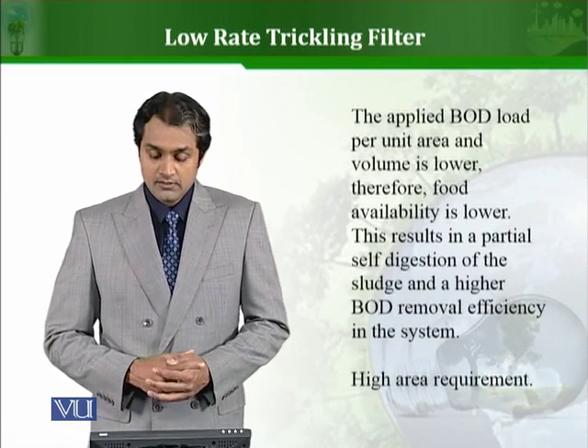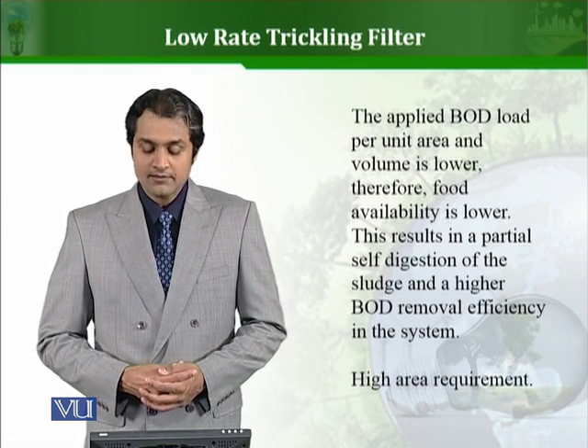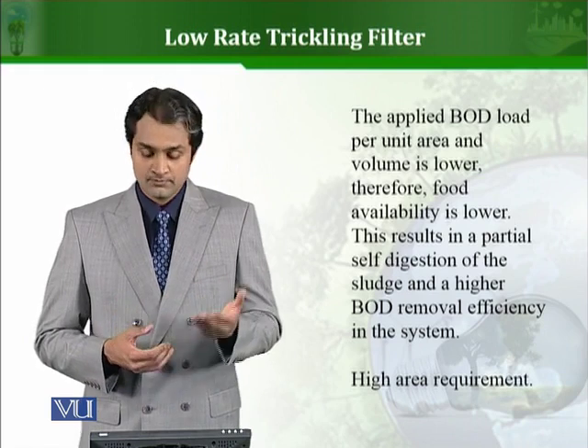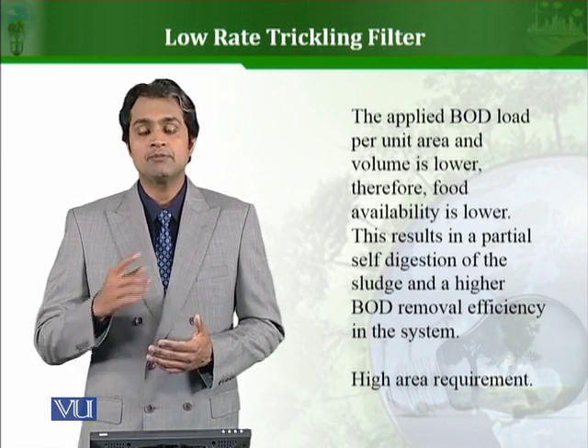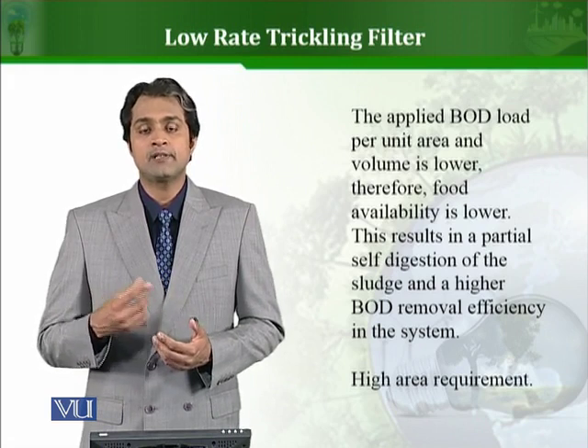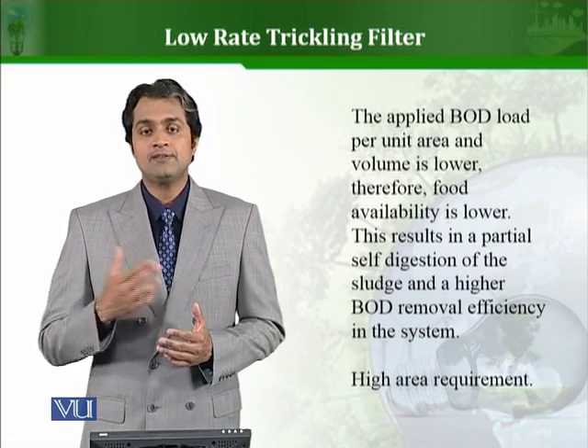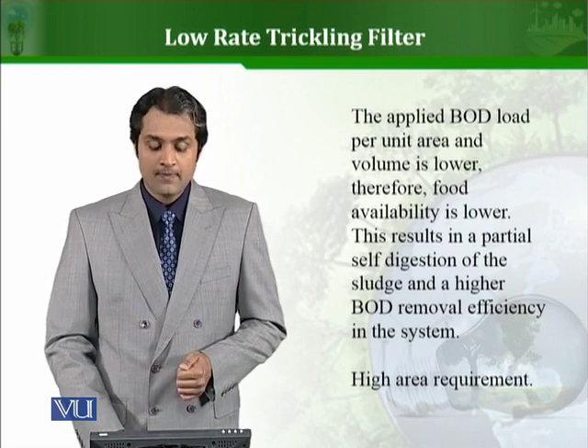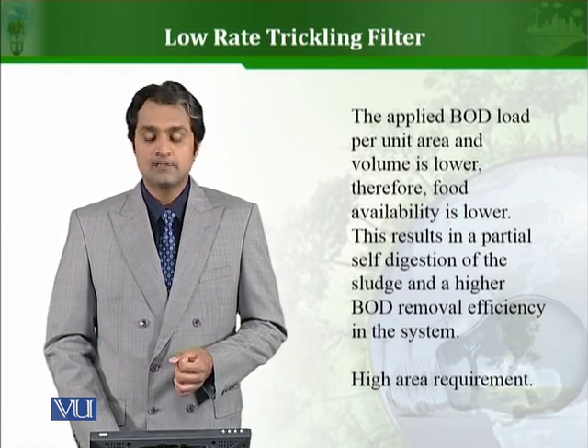The applied BOD load per unit area is lower — that is why it is called a low rate trickling filter. This results in partial self-digestion of the sludge. When the BOD rate is low, the organic content is less, so food for the biofilm is less. Bacteria start to die and the remaining bacteria utilize the dead cells, so the biomass stabilizes itself, increasing system efficiency. However, these systems require a much larger area to be installed.